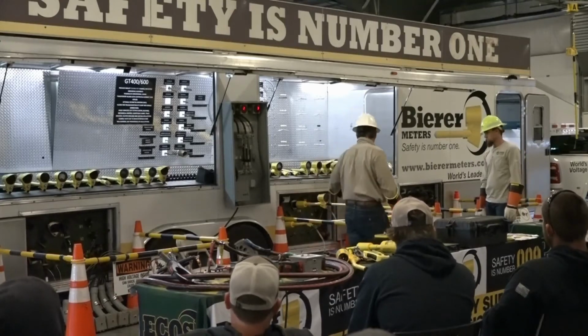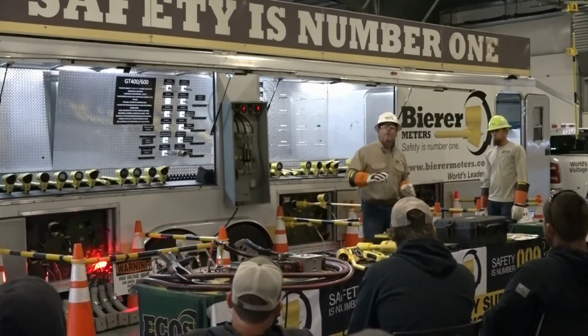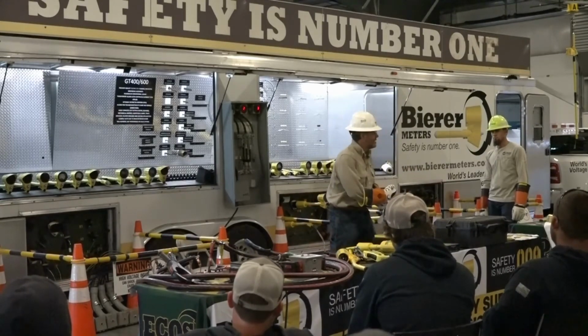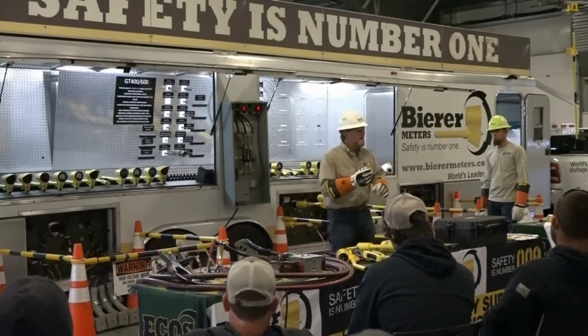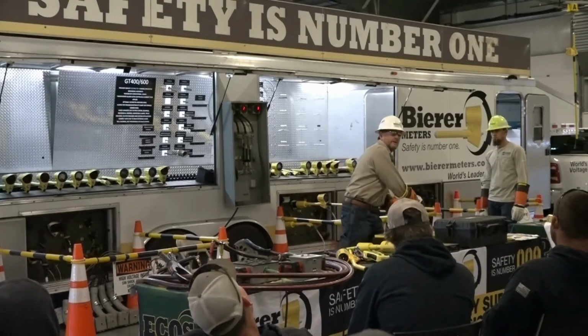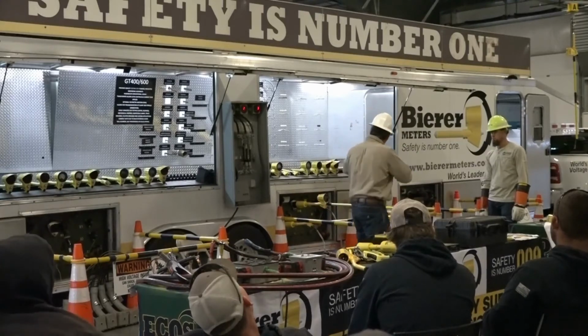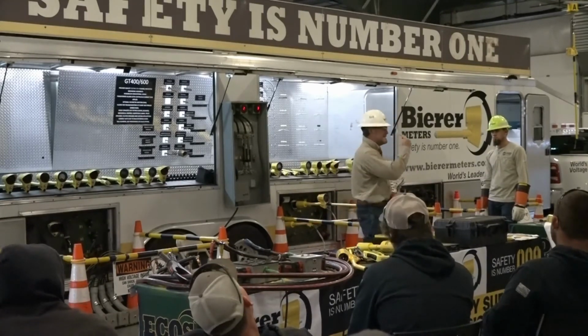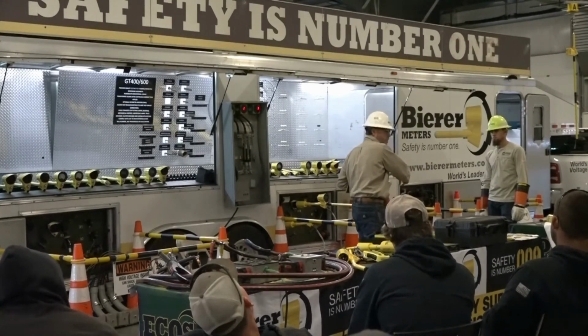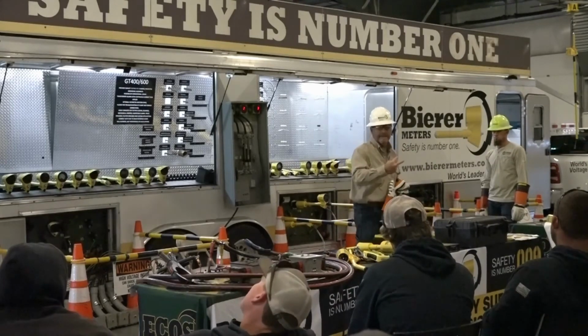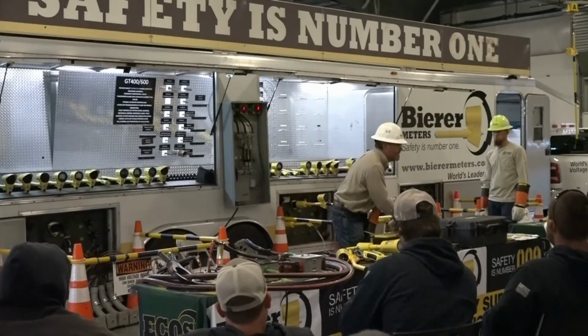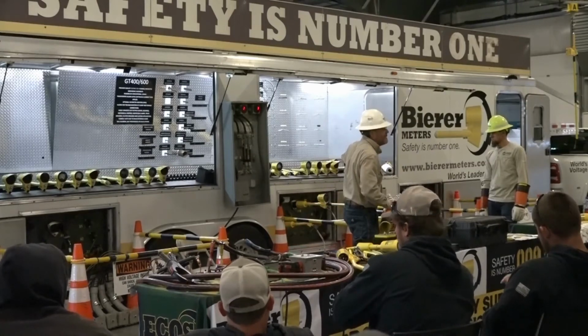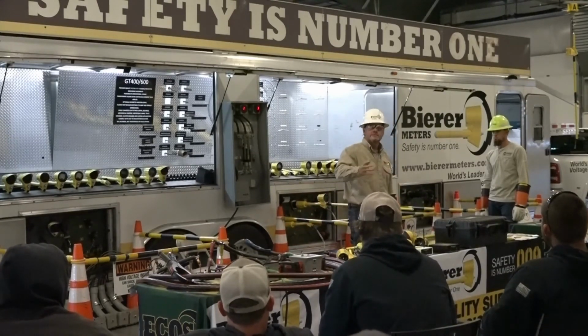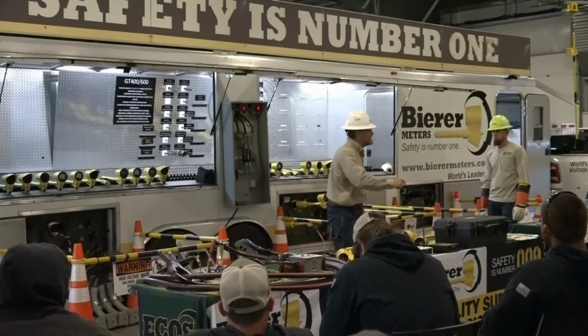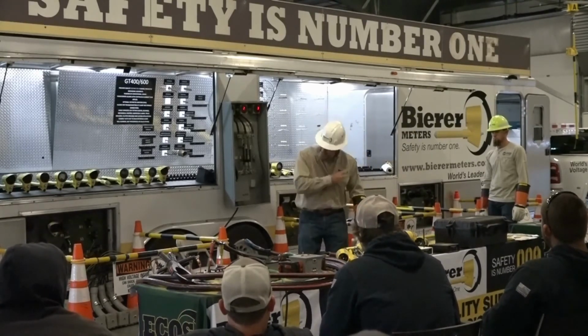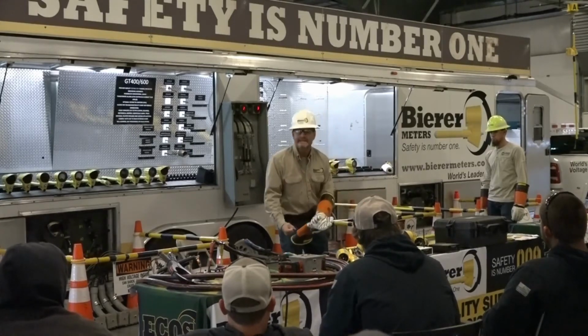Okay, so we know we're in phase. Now when you're phasing with anybody's tools, you always want to take your secondary probe off first, or if you're high potting, you always want to take that secondary probe off first to ground. The reason why is because when Dylan pulls that meter head off, he wants to verify that the tool is telling him that the device, the cord, and the secondary probe, the meter probe, that it's de-energized. But because it has resistors in both the secondary and the meter probe, Dylan knows it's not instant de-energization, it takes a couple seconds because of the resistors. Dylan wants confirmation that it is safe, it is de-energized, so he's always going to take the meter head off last, every time, every job site.